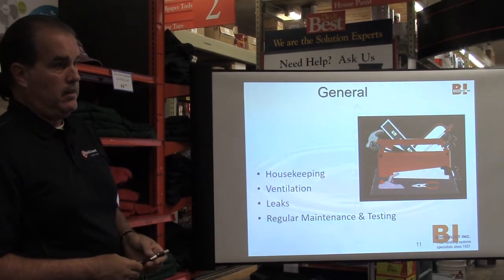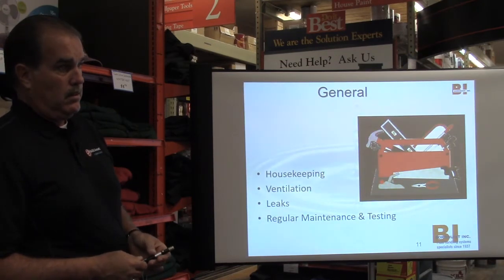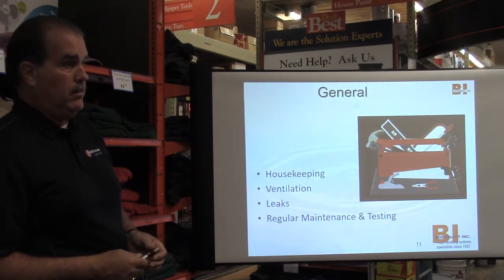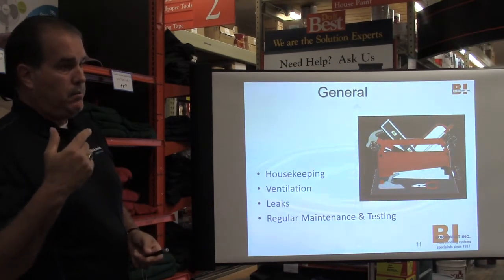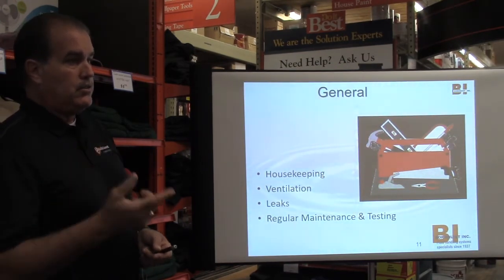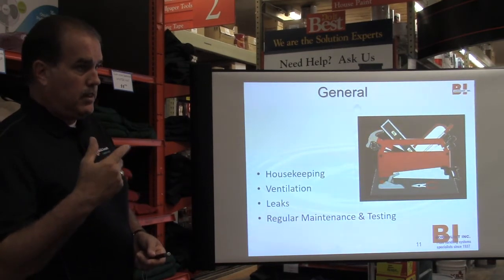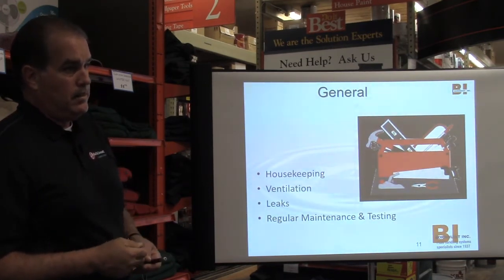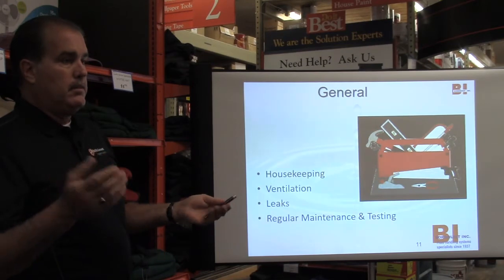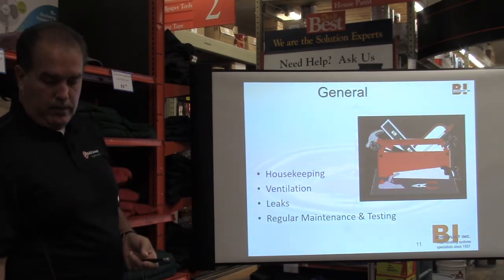Okay. About how often should you change the water then? Flush and change the water from the system? You should never have to. Should never have to. Okay. Because you got to understand, when you put new water in there, you introduce all those new chemicals, and you're actually going to make things worse. Yeah, he mentioned that. We had to because of a pipe. Yeah, well, that happens. When you're doing maintenance, you have to.